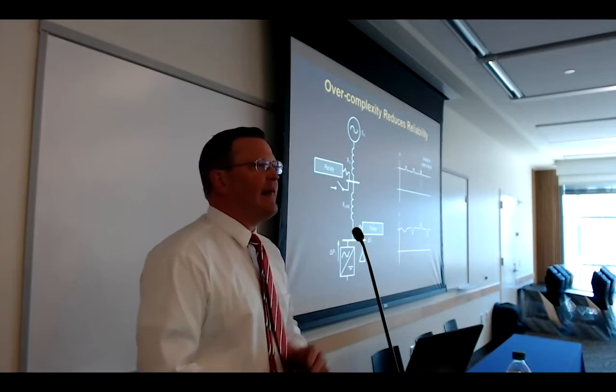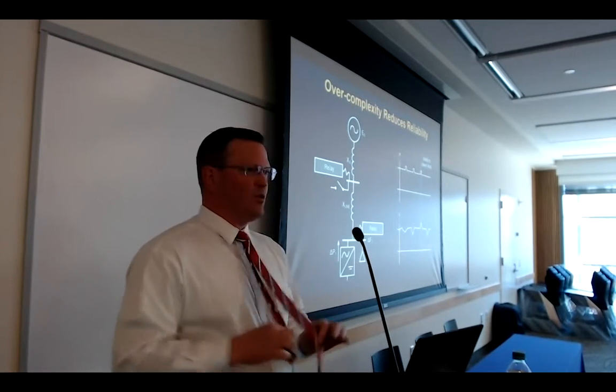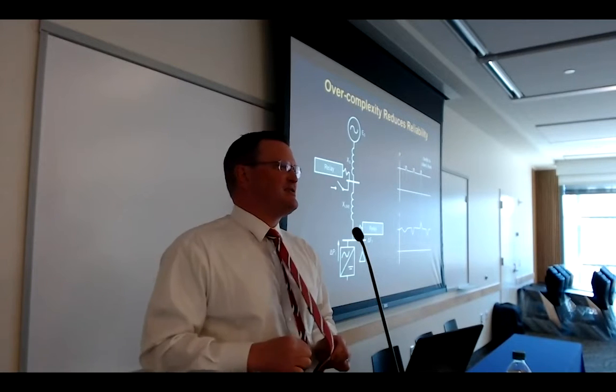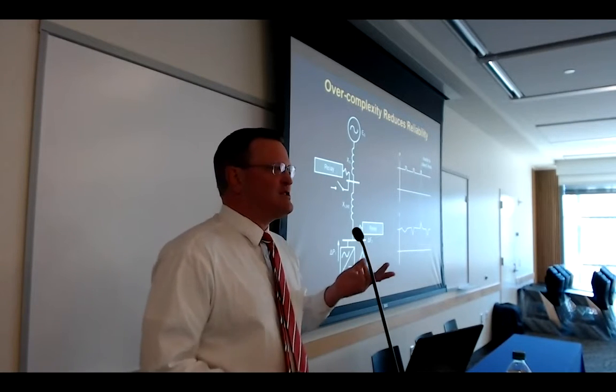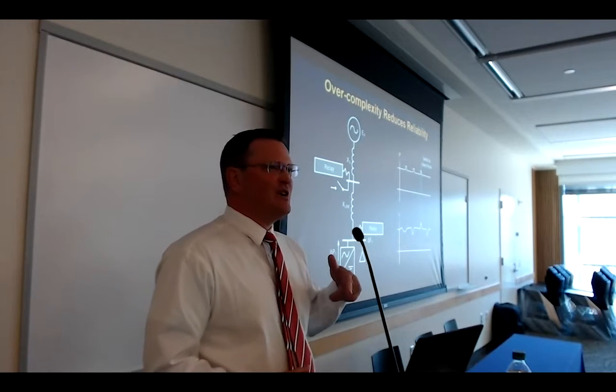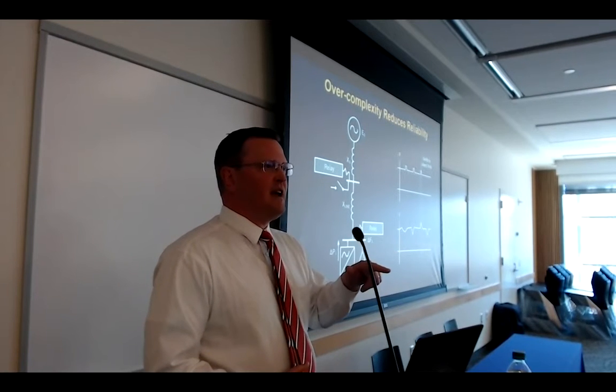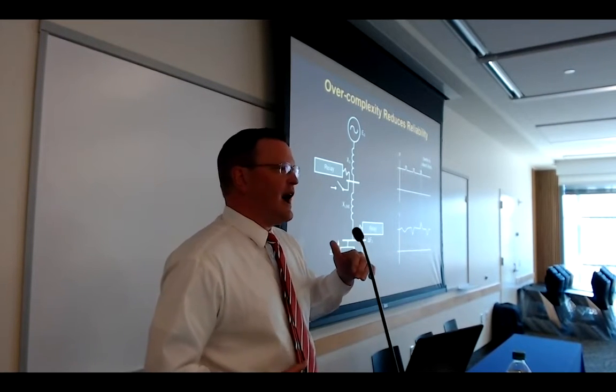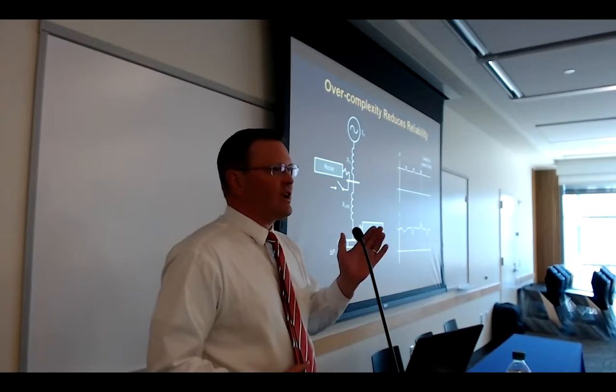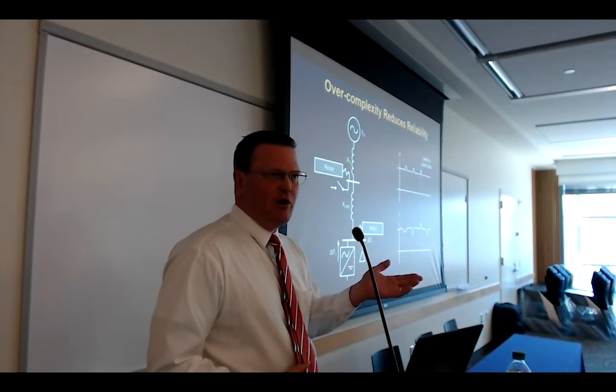So when these anti-islanding terms push against this very squishy grid, guess what you get? You get false operations. And then what happens? The inverter says, oh gee, I think I see an island, I switch to island forming mode, and quickly he trips out because he went over current, because he went out of step.